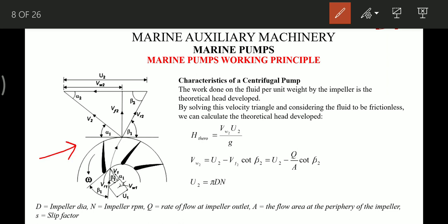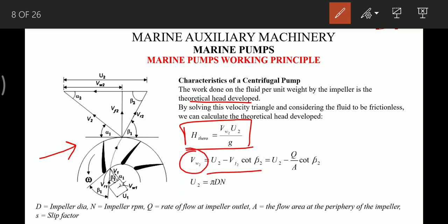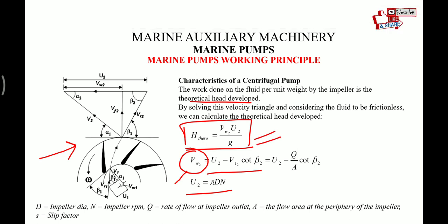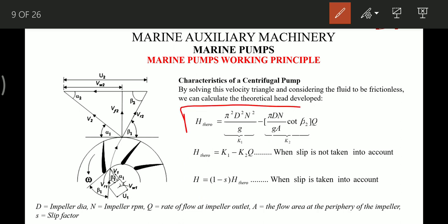Now for the centrifugal pump characteristic curve. Using the velocity triangle of the pump impeller, we can find the values of Vw2 and u2, where u2 = π·D·N, D being the impeller diameter and N the RPM. Substituting Vw2 and u2 into the equation, we find the theoretical head, where we call one term k1 and another k2.